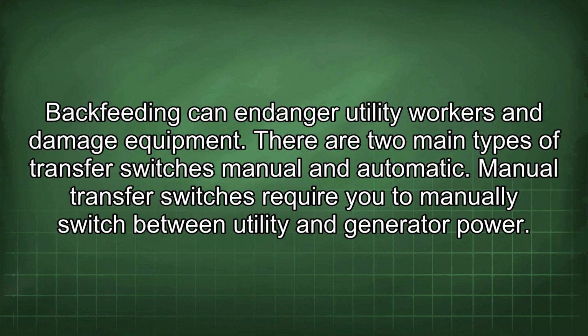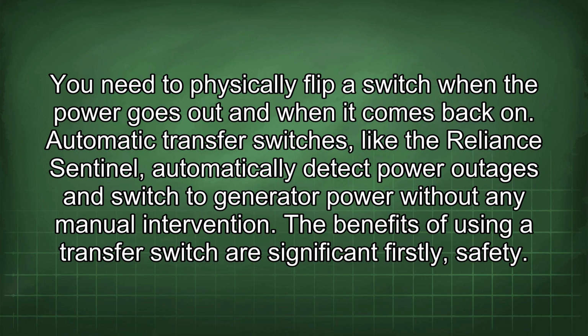There are two main types of transfer switches: manual and automatic. Manual transfer switches require you to manually switch between utility and generator power - you need to physically flip a switch when the power goes out and when it comes back on. Automatic transfer switches, like the Reliance Sentinel, automatically detect power outages and switch to generator power without any manual intervention.